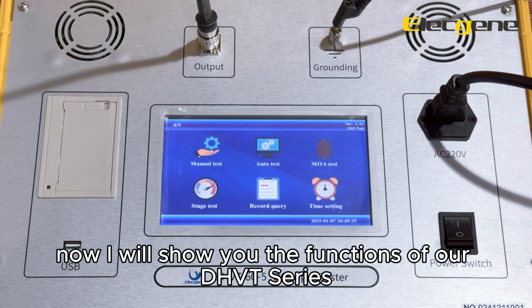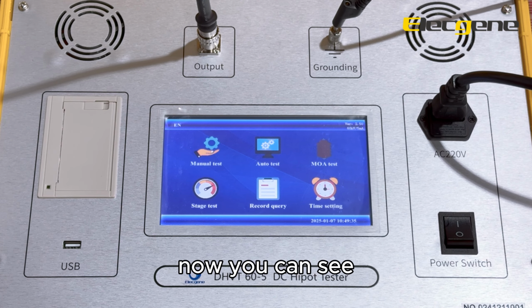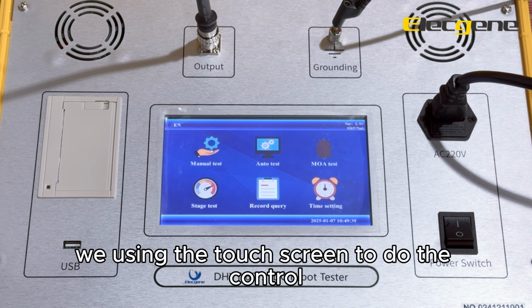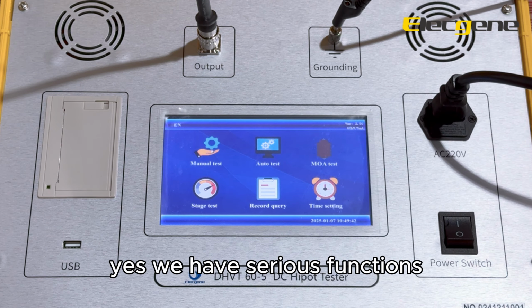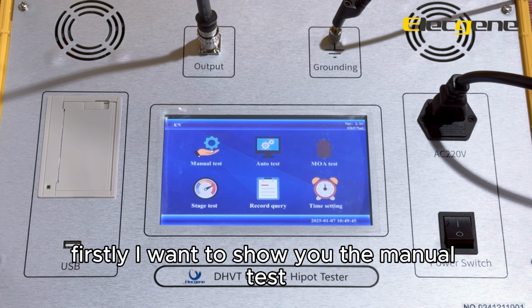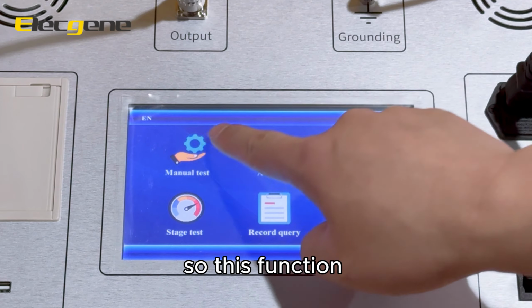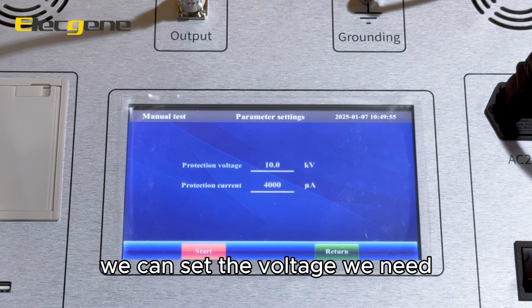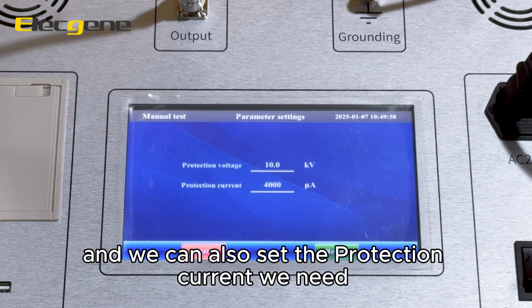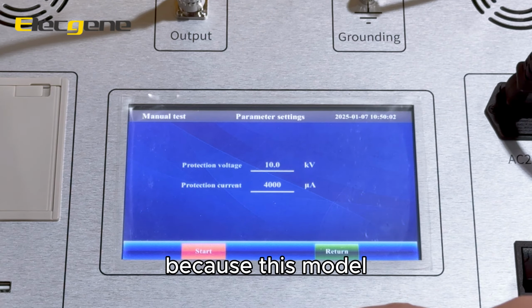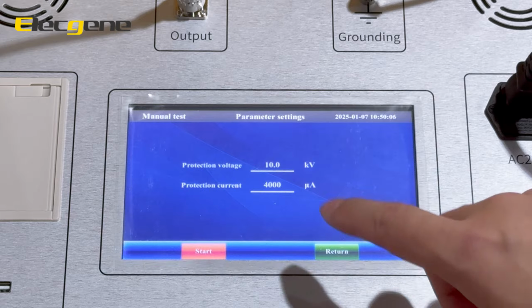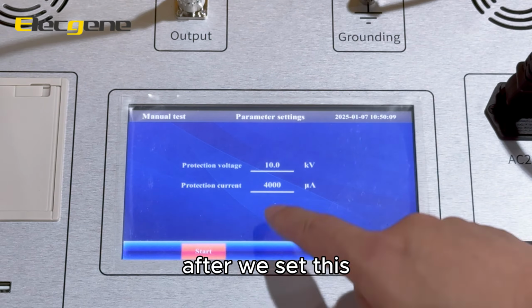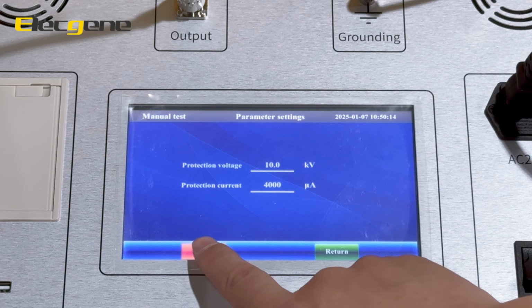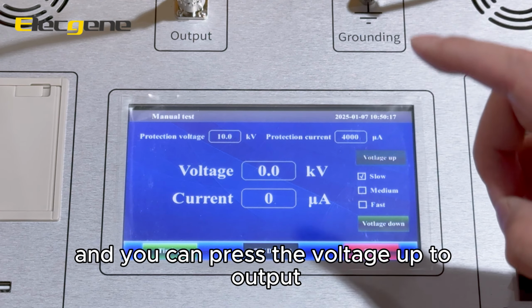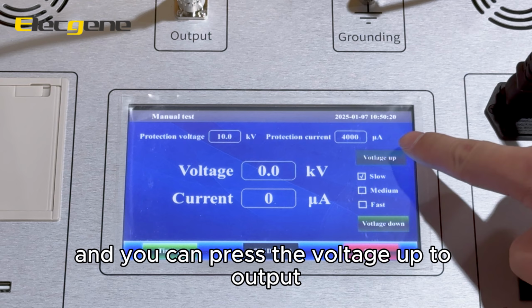My friends, now I will show you the functions of our DHVT series DC hipot. Now you can see we're using the touch screen to do the control. We have several functions. Firstly, I want to show you the manual test. It's here. With this function, we can set the voltage we need, and we can also set the protection current we need. Because this model's maximum current is 5 milliamps, here we can set. After we set this, for example, 10 kV and 4000 microamps, you press start, and you can press voltage up to output the voltage.